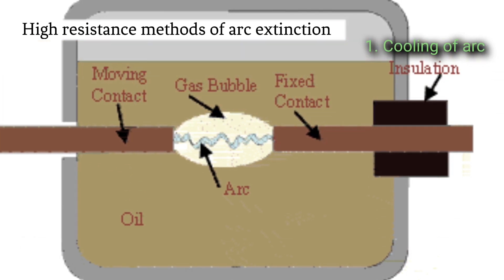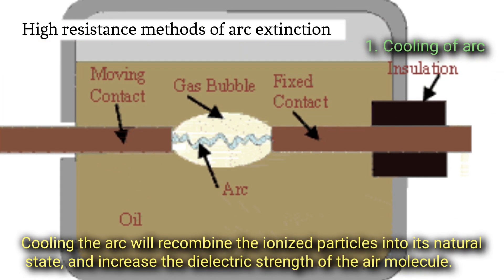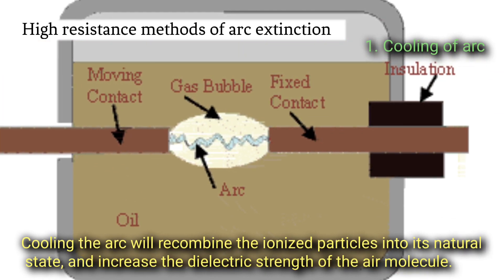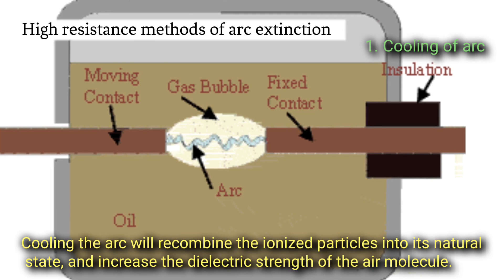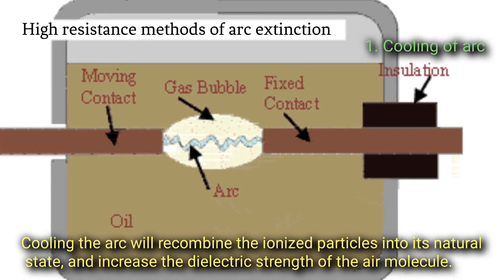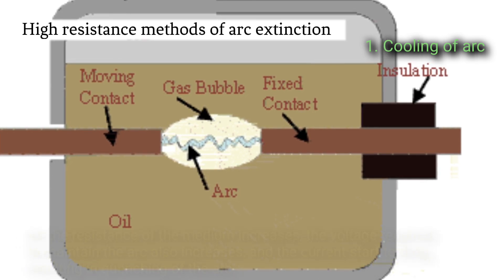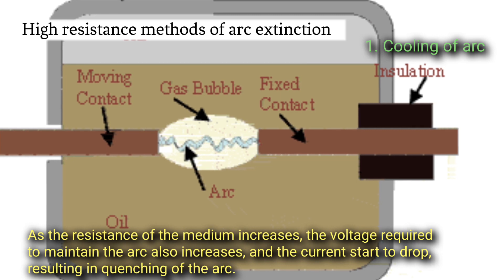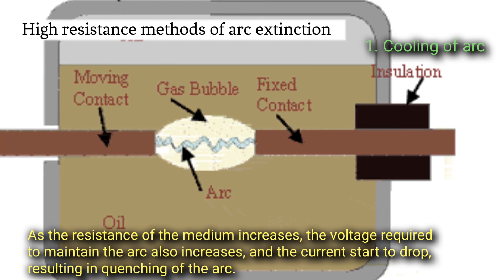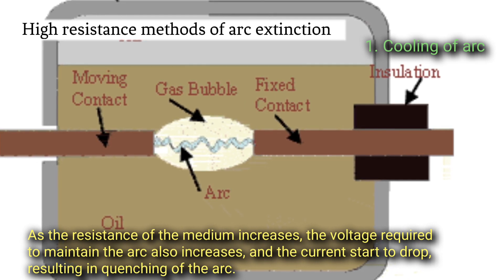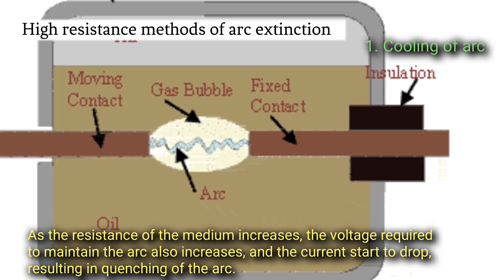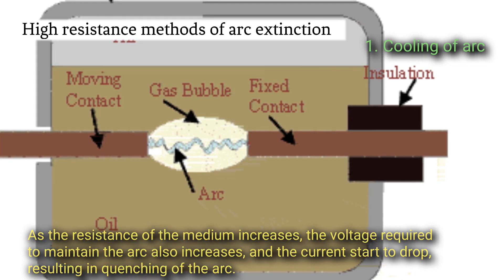Cooling of arc. Cooling the arc will recombine the ionized particles into their natural state and increase the dielectric strength of the air molecules. As the resistance of the medium increases, the voltage required to maintain the arc also increases, and the current starts to drop, resulting in quenching of the arc.